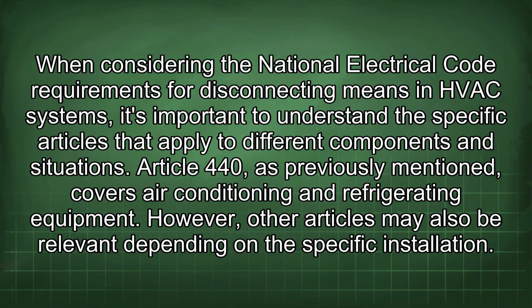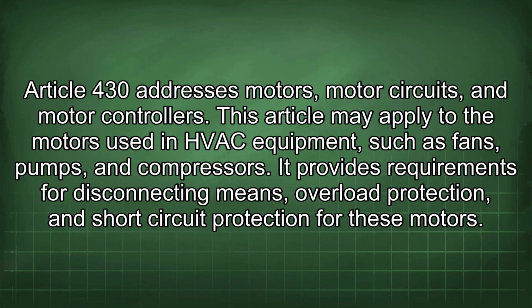Article 440, as previously mentioned, covers air conditioning and refrigerating equipment. However, other articles may also be relevant depending on the specific installation. Article 430 addresses motors, motor circuits, and motor controllers. This article may apply to the motors used in HVAC equipment such as fans, pumps, and compressors. It provides requirements for disconnecting means, overload protection, and short-circuit protection for these motors.